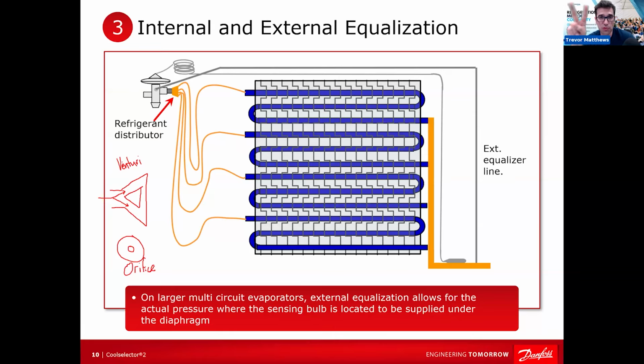And now if you plug these up, two things can happen. I've seen it both ways. This is one of the closing forces. So if you don't have a closing force, you could flood it. But if it plugs up, you also could get refrigerant in this line, which puts a lot of pressure underneath here, and it could also force it closed. So I've seen both, you know what I mean? Because I've read a lot of literature where people said it'll only flood if it's plugged or not. But we don't know if there's refrigerant under here heated up. So just be aware. Could be one of those.